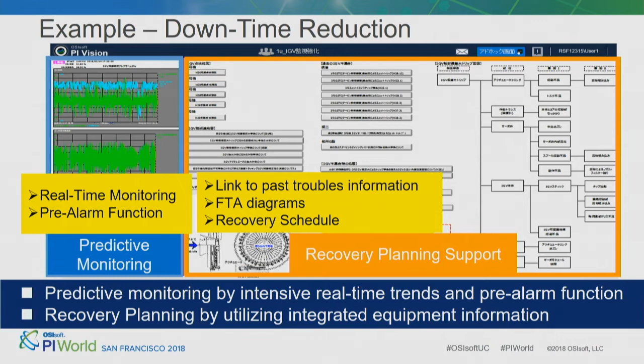Regarding inspection and replacement of forced draft fan equipment, we previously made decisions based on TBM. But with the PI system, we can calculate the actual operating hours of each piece of equipment and visualize remaining lifetime for inspection and replacement, as well as relevant parameters, in the same displays. We can then estimate the time to reach end of equipment life and prepare a proper maintenance plan based on CBM without any omissions.